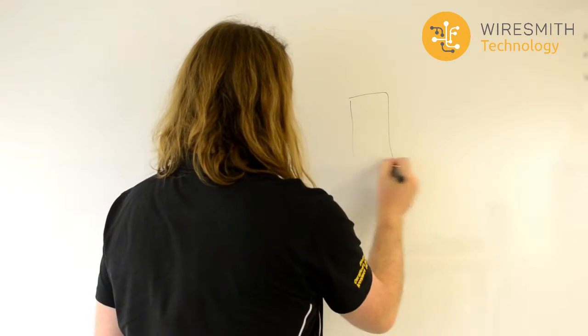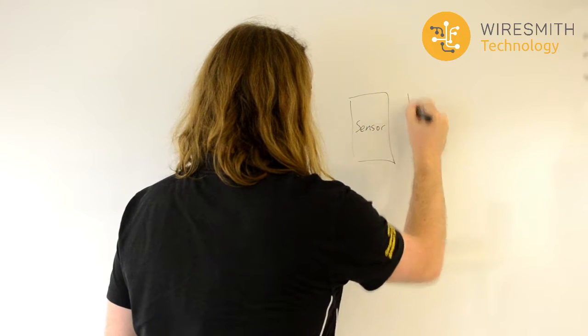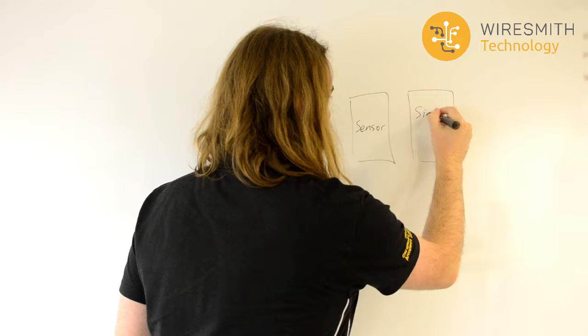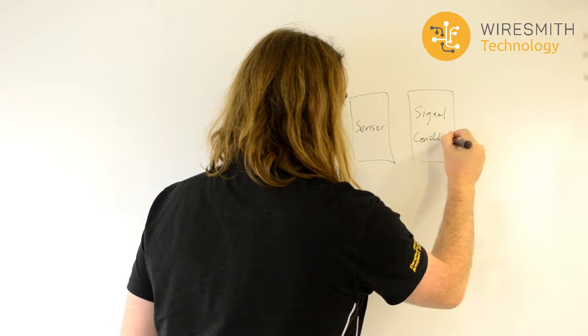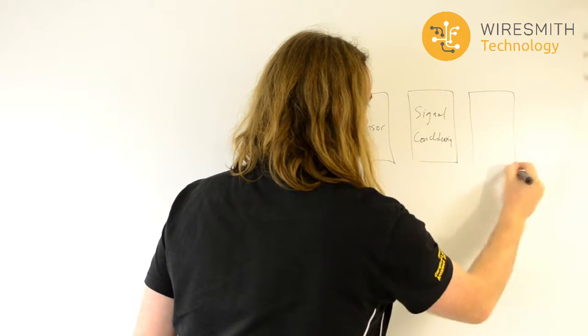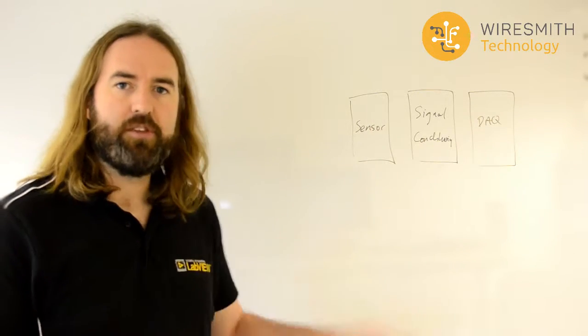There's a few things that factor into this that we want to consider, and hopefully we'll do a longer article on that one day. But for today I want to talk about system calibration. The idea behind system calibration is when we have our data acquisition system, there's actually a series of hardware elements involved. There's the sensor, there's some signal conditioning, and there's our data acquisition system, our DAQ card. And all of these can introduce their own errors, especially when sensors are more sophisticated, like, say, bridge-based pressure sensors.